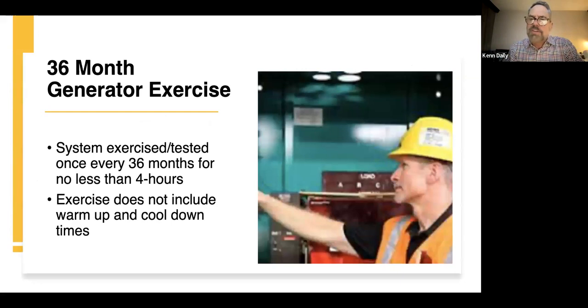Then there's the 36-month exercise, where once every 3 years you're running your generator under load for 4 hours. Again, for all these, whether it's the monthly or this exercise, the warm-up time and cool-down time don't count. So the monthly exercise is 30 minutes, but it's really how you run a generator for more like an hour. This is going to be more like a 4.5 hour run. That's what you're recording on your meter reading, how long it ran. If you just write down 30 minutes every month, or just write down 4 hours, that's not going to be enough time. That's not appropriate.